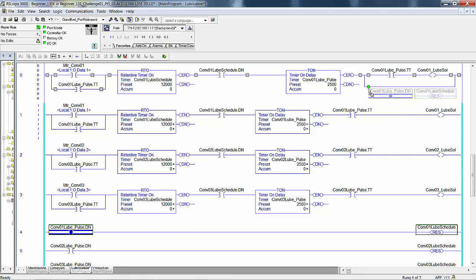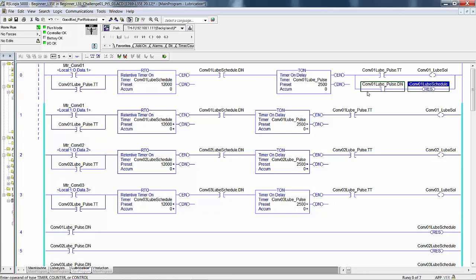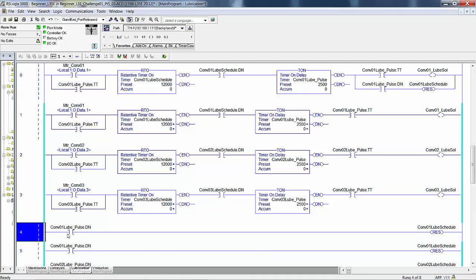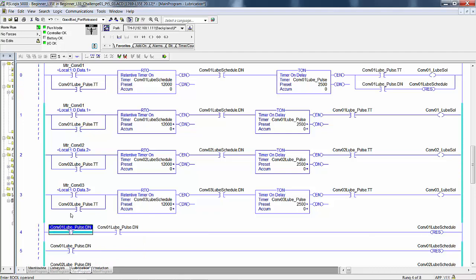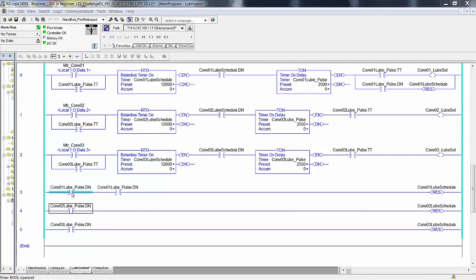Dragging this up here - remember I'm not moving it, I'm taking a copy because that rung's not in edit mode. It would look something like that. To render this rung workable I'm going to do this - it's a very easy way to cheat. So this says if the pulse is not done and it is done then reset - well you know they can't both be true, so we'll never reset loop 1. Let's check it out here to run motor 1 - we'll go to conveyors and turn on the entrance.